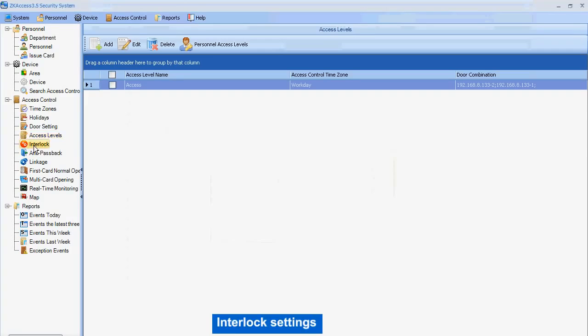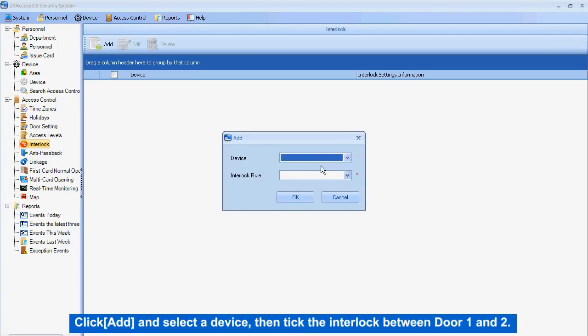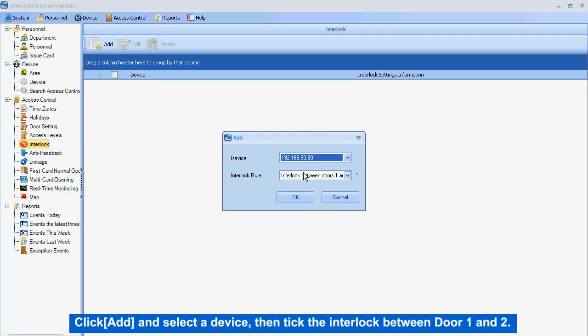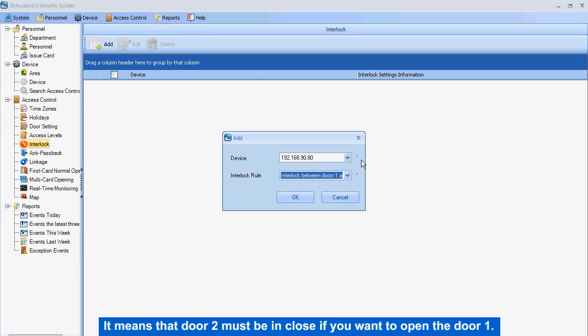Interlock settings. Click Add and select a device, then tick the interlock between door 1 and door 2. It means that door 2 must be closed if you want to open door 1.